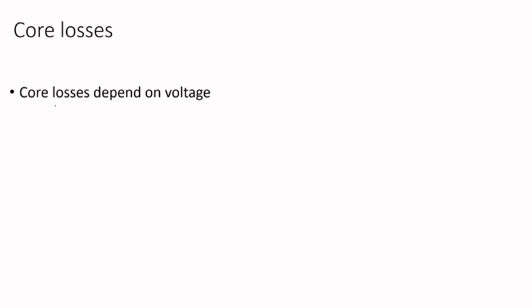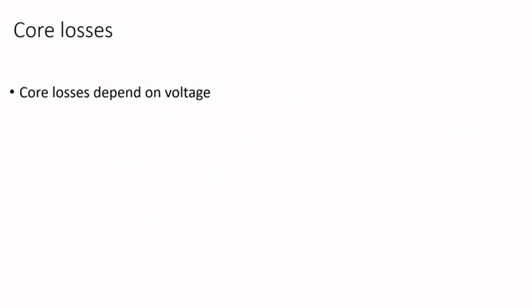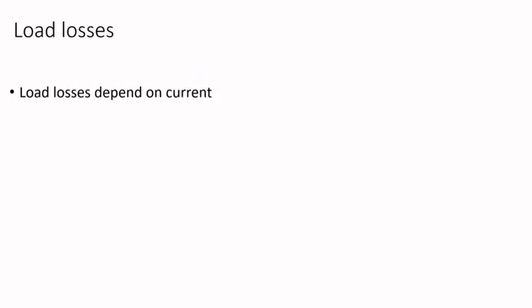Core losses depend on voltage. So as you increase voltage, core losses will increase. If you take the load losses, they depend on current because of I²R.